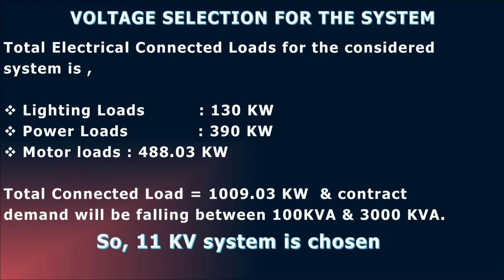And now coming to the total electrical connected load, the lighting loads are 130 kW, power loads are 390 kW, and the motor load is 488.03 kW. This I will be explaining later. So our total connected load will be 1009.03 kW, which means that our contract demand will be falling in between 100 and 3000 kVA. Based on the electricity supply code, we will be selecting the 11 kV supply voltage.